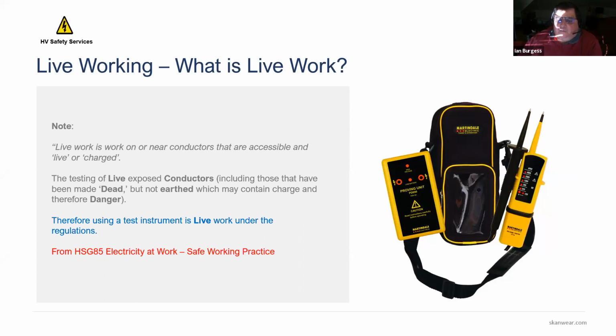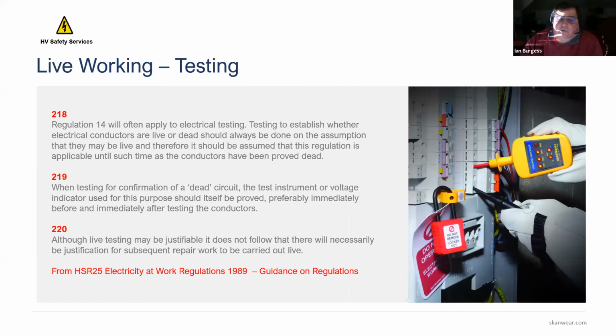And this is the sort of device you'd use for LV, an LV voltmeter or LV tester, with a proving unit to prove the correct function of the equipment. And it's recommended that testing devices are tested before and after testing to confirm they still work. So Regulation 14 allows this testing to take place. And as I said, testing before and after. And although you may be able to justify live testing, it doesn't necessarily follow that you'll be able to justify that the work can be done live.